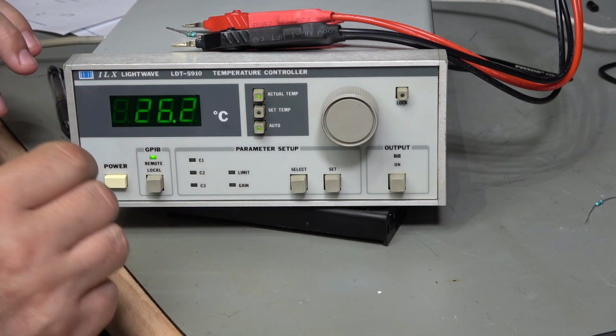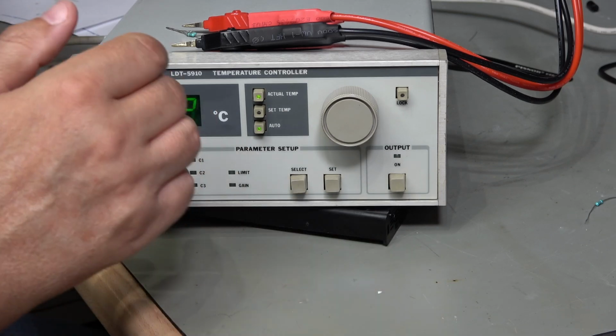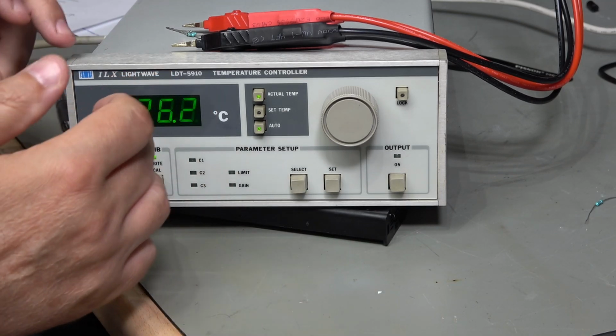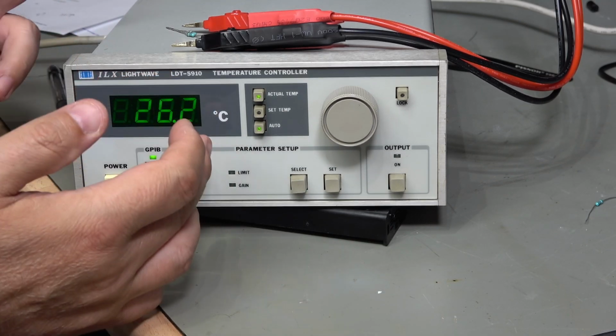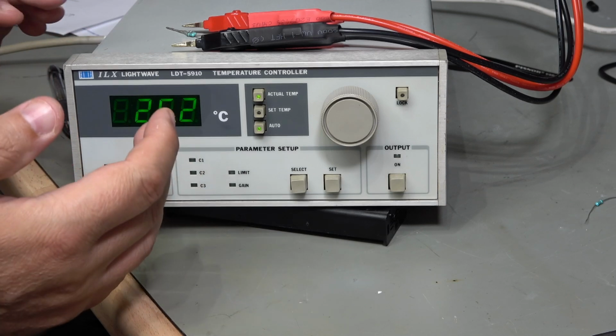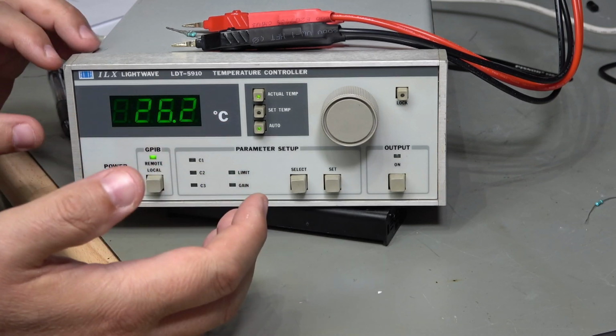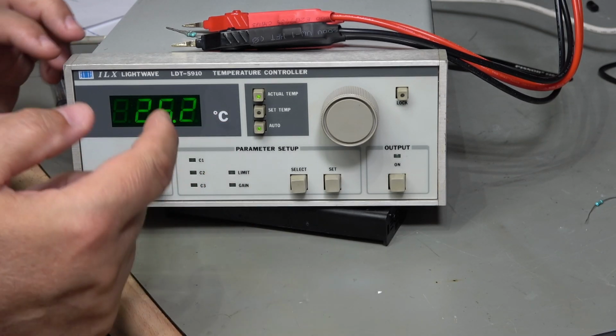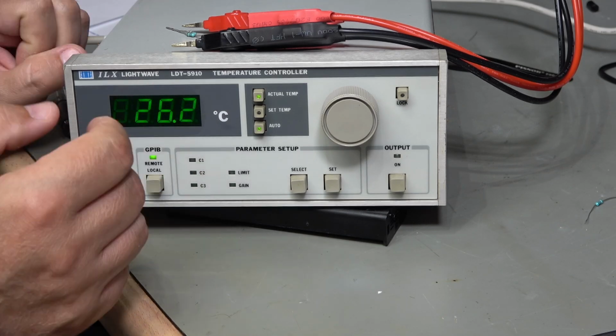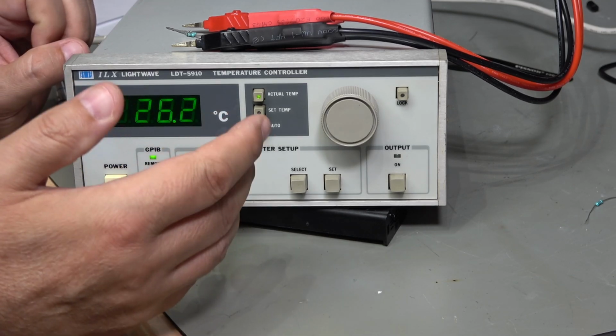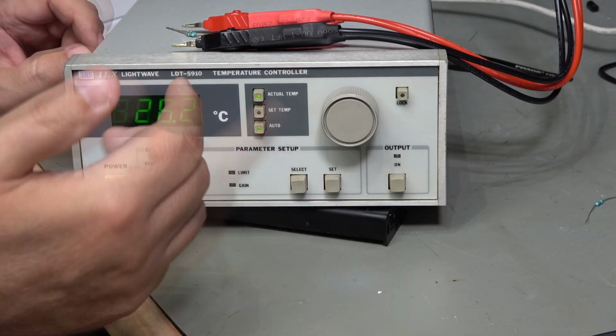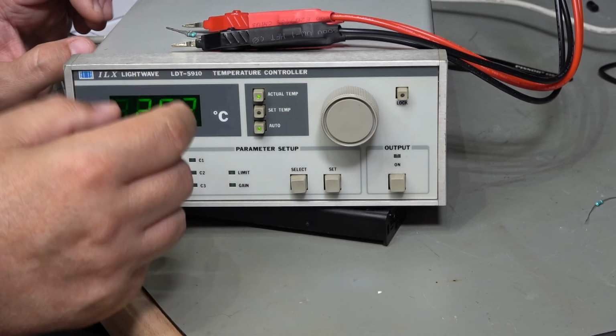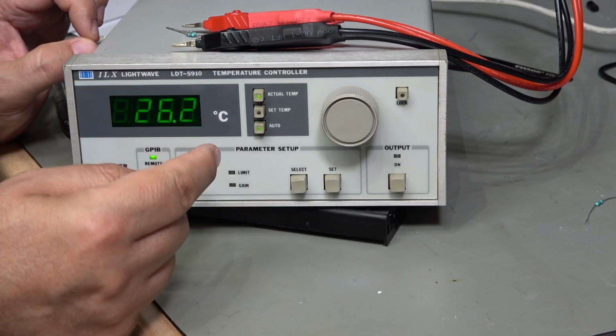We want to display what the device thinks that resistance is, because the way we're going to do this is that we're going to look at the resistance that it thinks it is, and we're going to work out by what percentage or what proportion that is incorrect. We're then going to pull up a parameter, so there's a coefficient in there which is used in the maths to change the voltage reading that it's doing on the op amp into a resistance reading. We need to trim that to get it right. We need to do that for both current ranges.